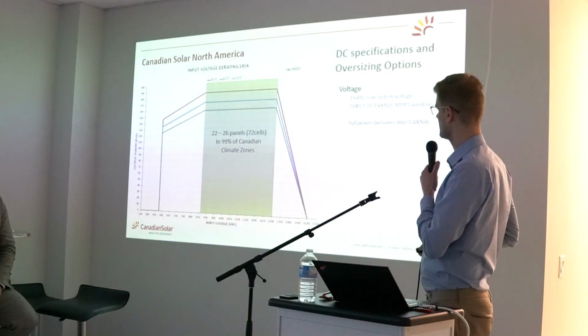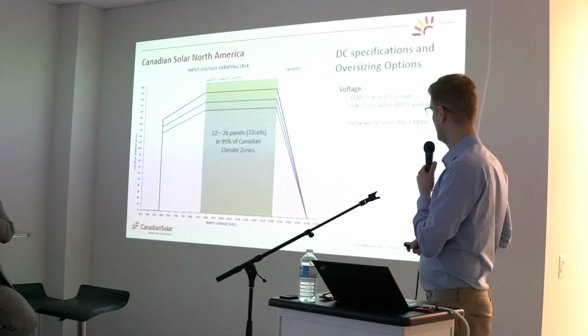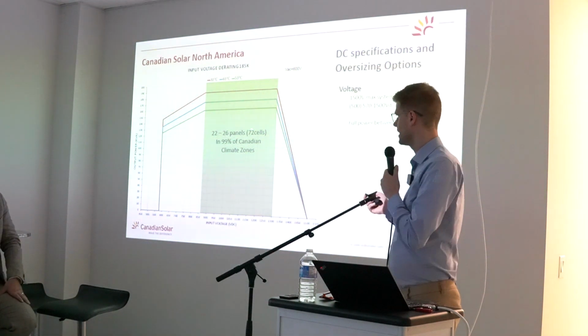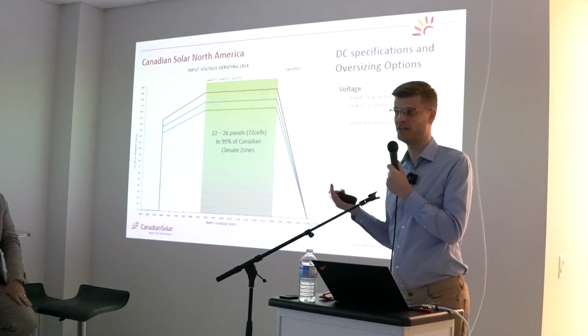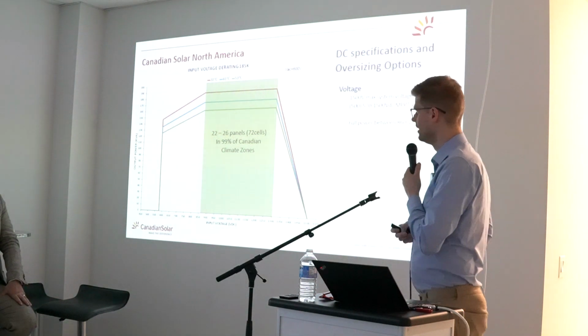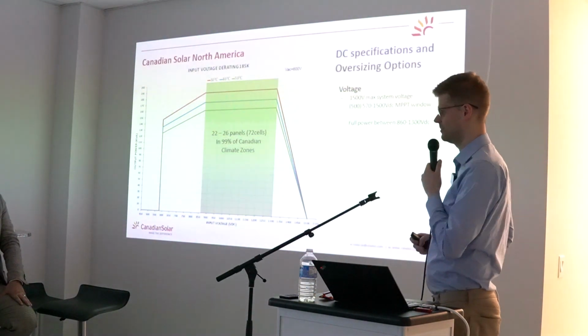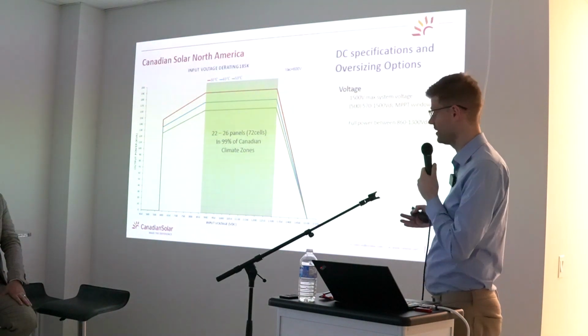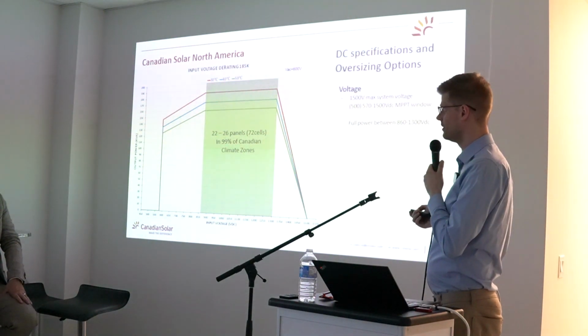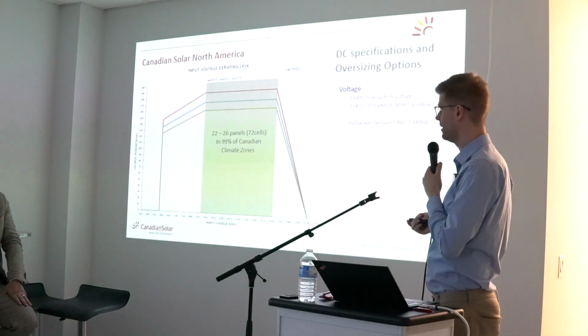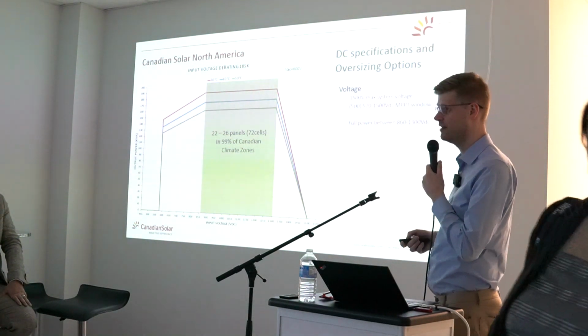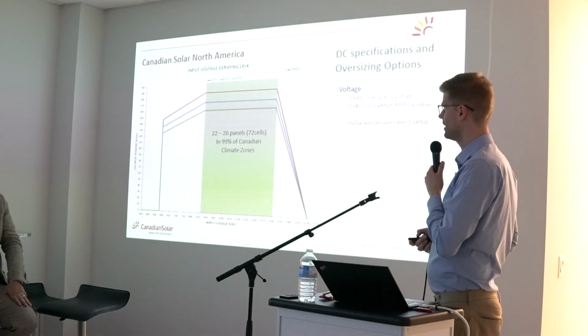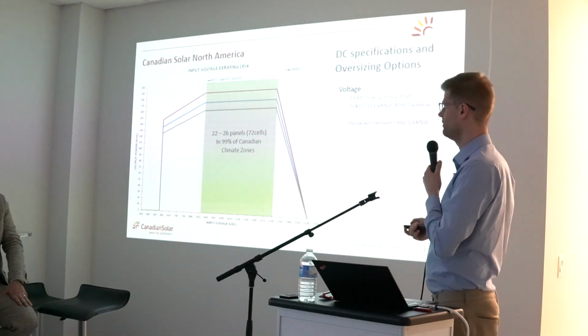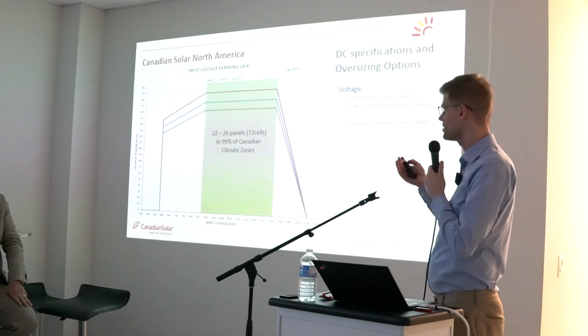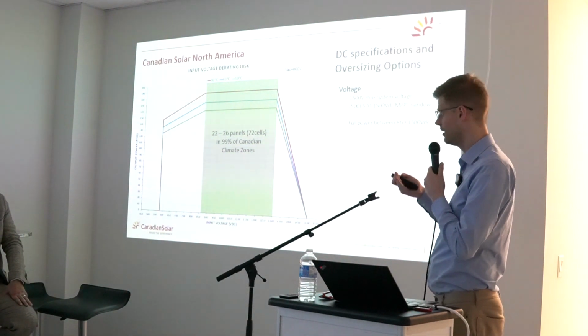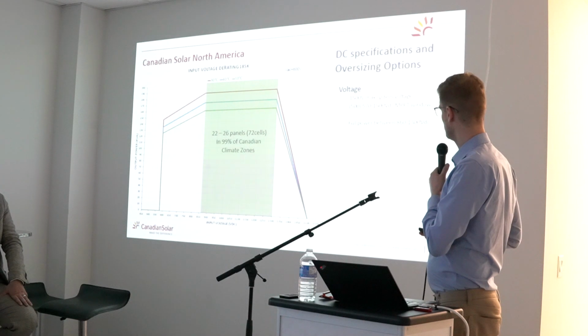The starting voltage is here at 570 volts. So for most designs, as you can see here, we have about 22 to 26 panels, depending a little bit on the location you install that system. It's different in northern Alberta than it is in southern Ontario. Southern Ontario is very common to have 24, maybe 25 panels of the typical 72 cell standard in a string. If you go to very north and very, very cold environments, then you have to reduce that a little bit to still stay within the voltage limits if it gets to the record cold situations.